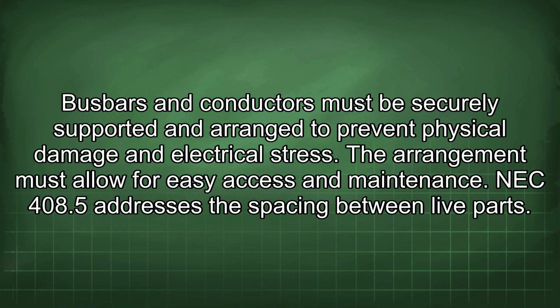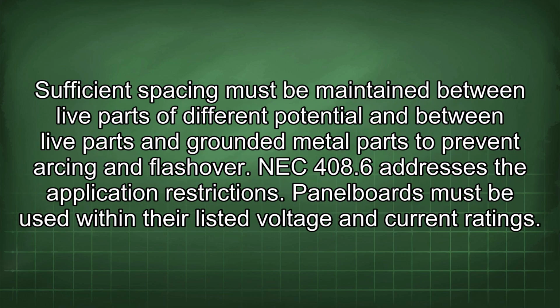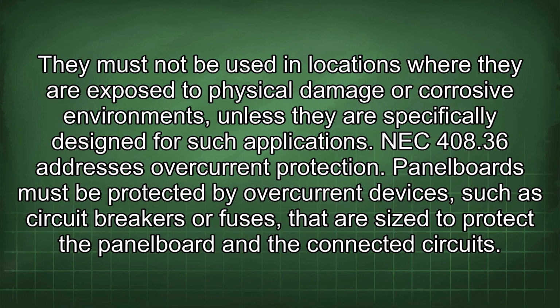NEC 408.5 addresses the spacing between live parts. Sufficient spacing must be maintained between live parts of different potential and between live parts and grounded metal parts to prevent arcing and flashover. NEC 408.6 addresses the application restrictions. Panel boards must be used within their listed voltage and current ratings. They must not be used in locations where they are exposed to physical damage or corrosive environments unless they are specifically designed for such applications.